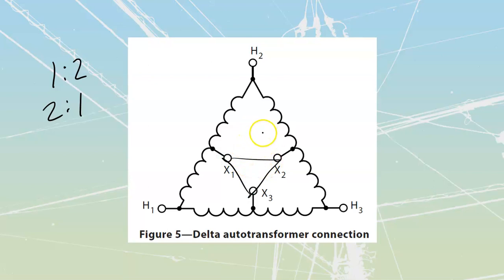If I rotate that triangle through, if I get a triangle going from here to here to here, I am going to be at 50%, but if I start rotating it this way, then I'm going to be slightly larger, etc. And then I can continue rotating this triangle as I go along from tap to tap to tap, which is going to make this triangle larger, larger, larger, but at no point will it ever get greater than a 1:2 ratio. If I would continue to rotate this through the taps, eventually I would come to a point where my secondary tap would be the same as my primary.